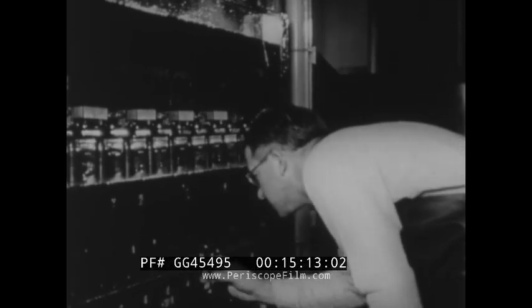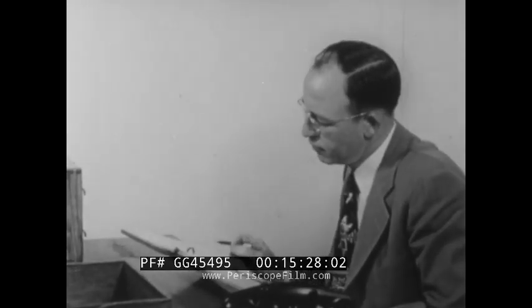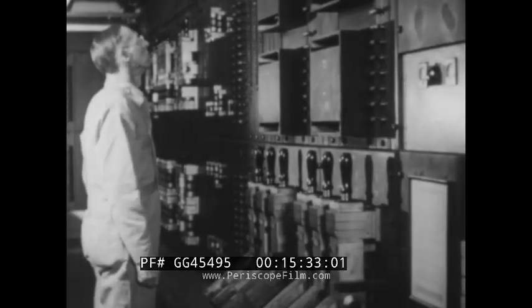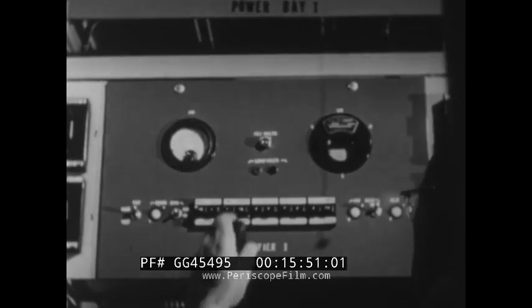Common troubles are evidences of deterioration that need remedial action. Sulfation is evidenced by low gravity and low voltage readings, and found by analyzing the battery records. This condition in its earlier stages can be corrected by boost charging. Sediment can be seen in a glass jar cell. Normal amounts of sediment will be found under cycle charging; however, sediment found in floated batteries indicates incorrect float voltages. This illustrates the importance of keeping the regulating equipment in proper adjustment.